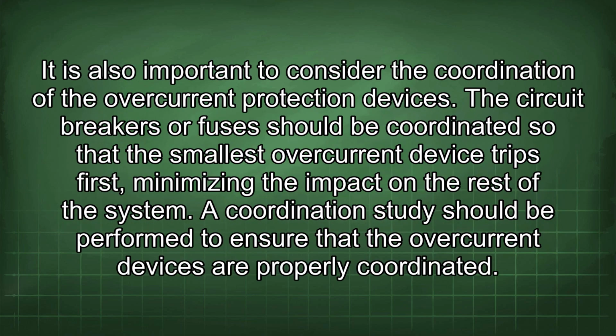It is also important to consider the coordination of the overcurrent protection devices. The circuit breakers or fuses should be coordinated so that the smallest overcurrent device trips first, minimizing the impact on the rest of the system. A coordination study should be performed to ensure that the overcurrent devices are properly coordinated.